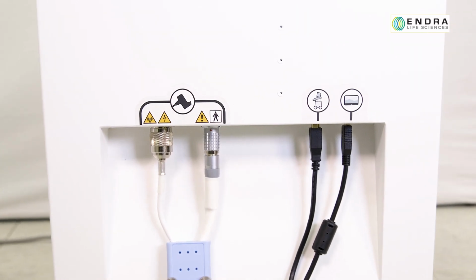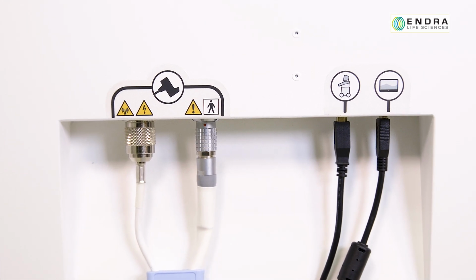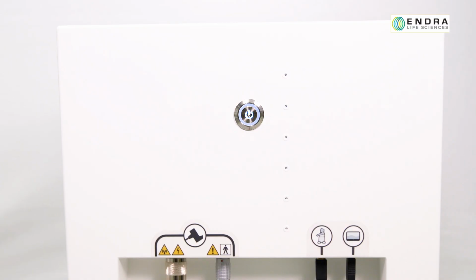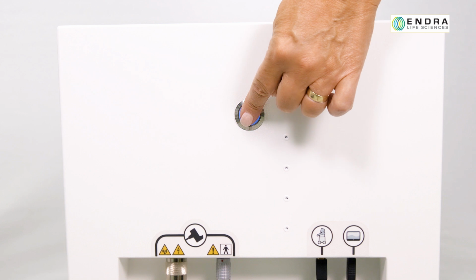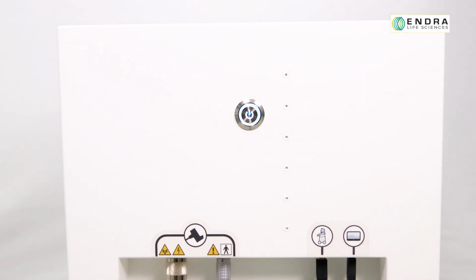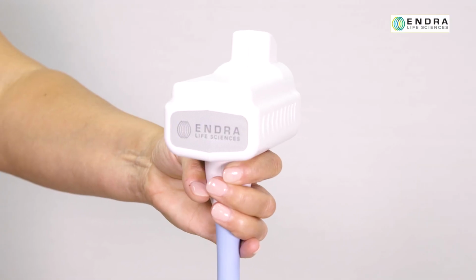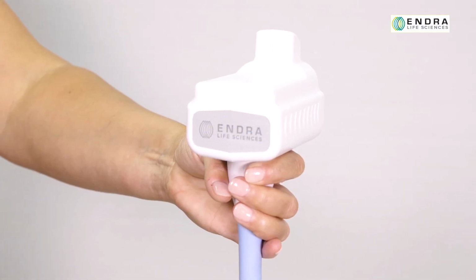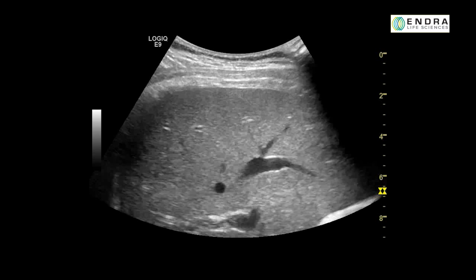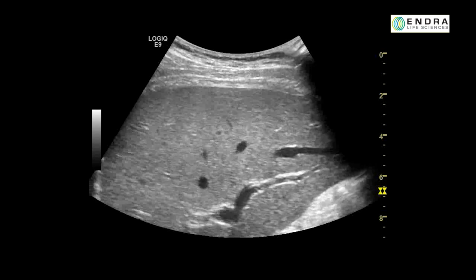The FLIP probe, touchscreen monitor, and ultrasound system are all connected to the console. To power up the TAEUS system, push the flashing white soft power switch on the front of the console. When powered up, the soft power switch turns solid white, and the status indicator on the FLIP probe flashes blue while it warms up. First, configure the ultrasound system for B-mode scanning.